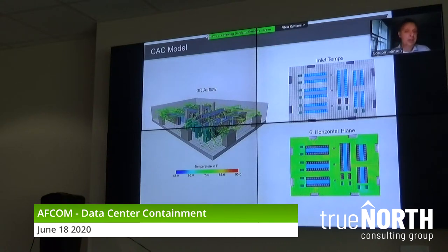Let's add cold aisle containment and see how we fix things very quickly. If you look at the airflow model on the left, I've added cold aisle containment pods to the entire data center. Notice the hot air. You see the air streams returning below the drop ceiling, but they're returning over the equipment back to the returns on the CRAH units. Notice how consistent that temperature is. There's no 95, 100 degree temperature anymore. Now look at the right-hand corner. My inlet temperatures, they're all 62, 63 degrees in my data center. Look at my lower right-hand corner, the 6-foot horizontal temperature plane. No hot air is getting into the cold aisles. I've separated the two. My cold aisles are cold, and basically the rest of my data center is one big hot aisle.